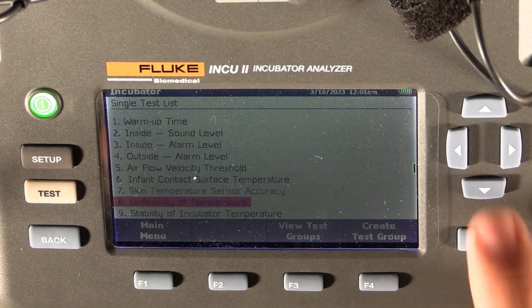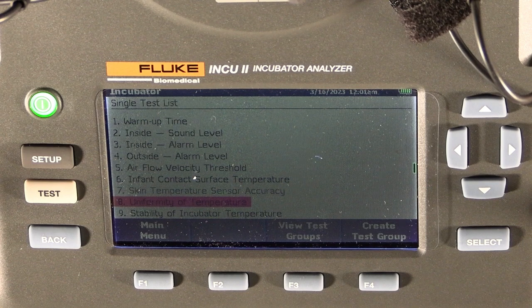Then number 8, uniformity of temperature. What we want to know here is whether the feet of the baby, the head of the baby, or the tummy of the baby are all at the same temperature, that we do not have a warm and a cold area inside our hood. So we'll be making use of all 5 of the sensors and then compare the temperature between the 5 of them.